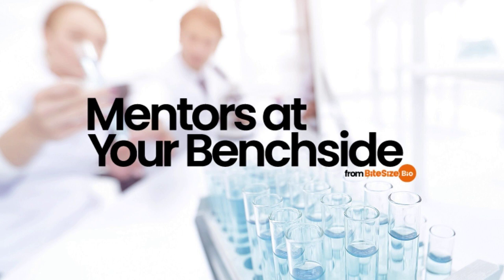What do you do when crystals form on the pH meter? It's a common enough occurrence. You come to the pH meter and it's bejeweled with rock-hard crystals. Those crystals are potassium chloride, and they form when the potassium chloride solution evaporates. Here's what to do. Gently scrape off any external crystals, soak the probe in warm water to dissolve the crystals, refill the probe with 3 molar potassium chloride, and check the function of the probe by measuring the pH of calibration solutions. And that's it for maintaining and using a pH meter correctly.